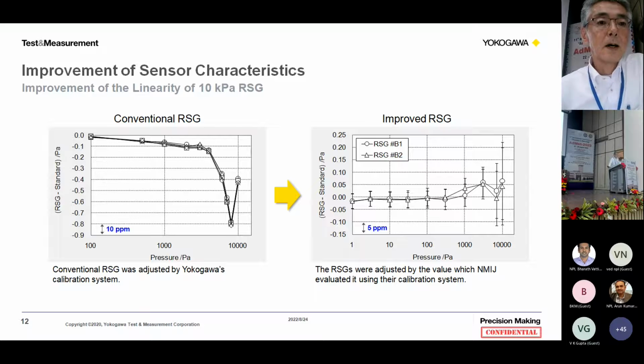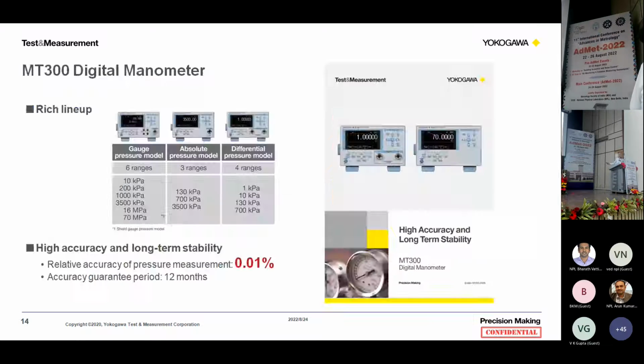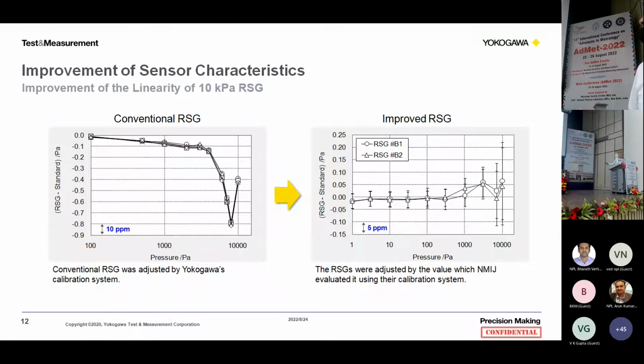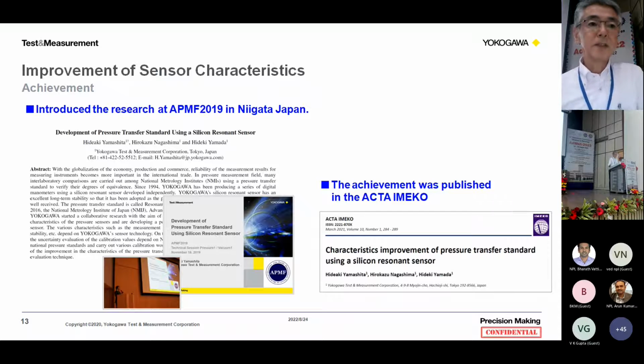As a result, the left-hand side is a conventional sensor, calibrated and adjusted by the Yokogawa calibration system. And the right-hand side is the improved sensor, calibrated by the NMIJ calibration system. As you can see, there is significant improvement. These activities were introduced at the APMF, Asia Pacific Measurement Forum in Niigata, Japan, and the achievement was also published in the ACTA IMEKO.